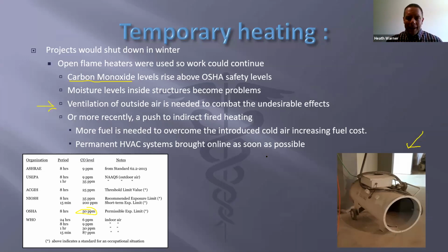So overcoming that led to indirect fired units. You basically set the unit outside. That way you don't have to worry about the combustion inside of the work area. And everybody's happier because you don't have the CO level, except for that heating unit that sits outside. 30% of every BTU that you create outside of the work area just overcomes ambient. So fuel costs have increased in the last few years by at least 30% per month, just overcoming the issues that you have with combustion.